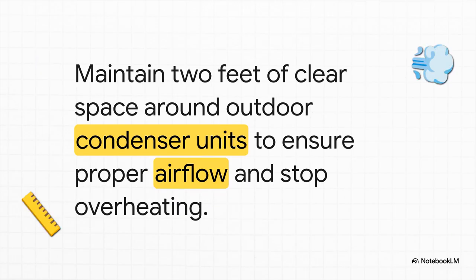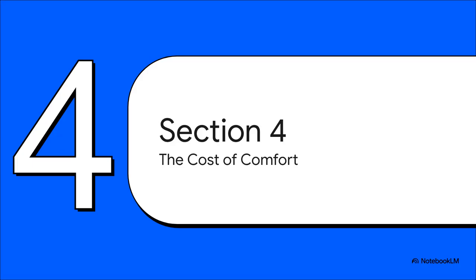And then we have the 2-foot rule. This is your absolute baseline defense against snow, shrubs, and debris that choke your system and force it to work harder. The outdoor unit literally needs to breathe. If you let landscaping overgrow or allow snow to pile up against it during those brutal winters, you choke off the airflow. This forces the compressor to overheat, absolutely tanking its efficiency and ultimately killing the unit well before its expected 15 to 20-year lifespan. So keep a 2-foot perimeter perfectly clear, always. Which brings us to Section 4, the cost of comfort.